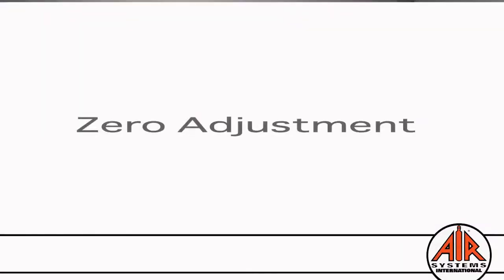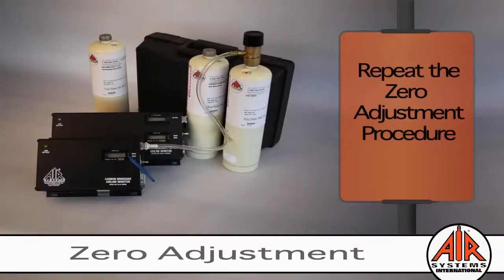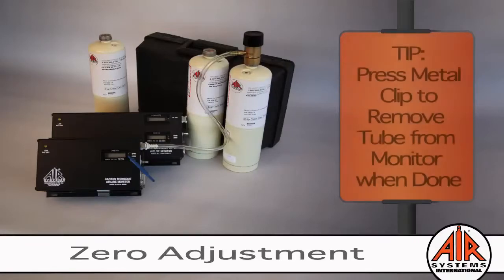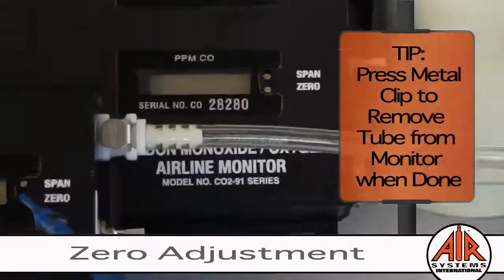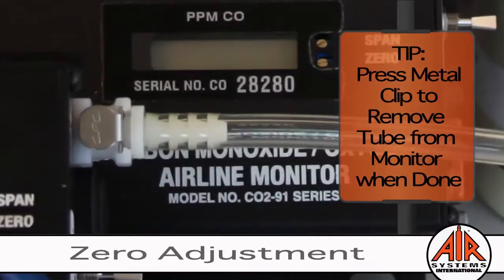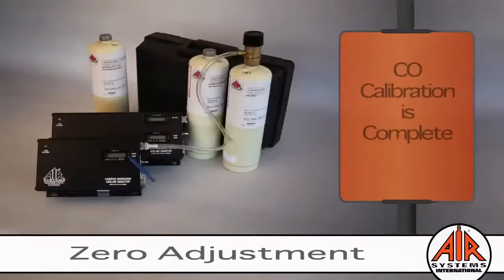Phase 3 of the calibration process is the zero adjustment. Repeat the zero adjustment procedure to ensure instrument accuracy. Now a tip for you: press the metal clip to remove the tube from the monitor when done. If you have a carbon monoxide monitor, the calibration process is complete. You may turn the monitor off.